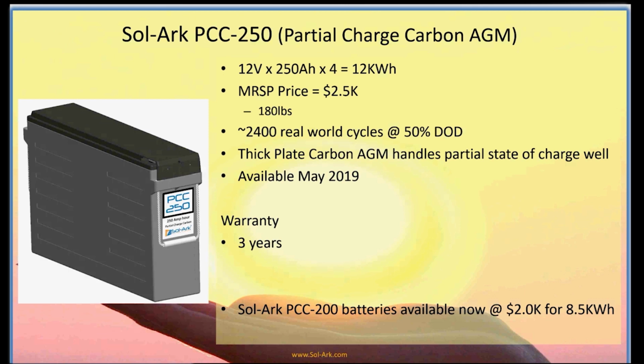Okay. Do they interlock when stacked? No, there are some battery racks out there. We offer a battery rack that goes up to 16 batteries or 4 strings. Okay. So any questions that I may have missed? Okay, I think for earthquake prep, then use a rack. Yes, they can be bolted to the ground. So there are some racks that are earthquake proof to a level, and so you can use a rack there too. A lot of times I just put them on the ground though.